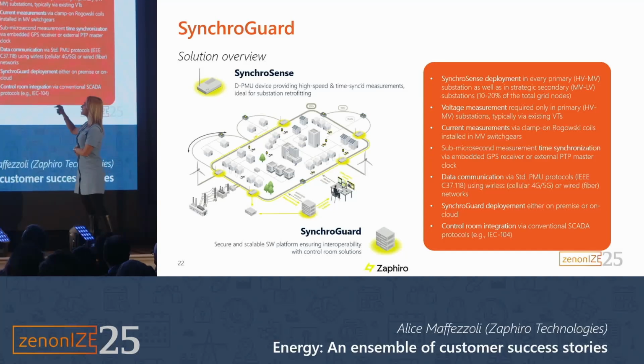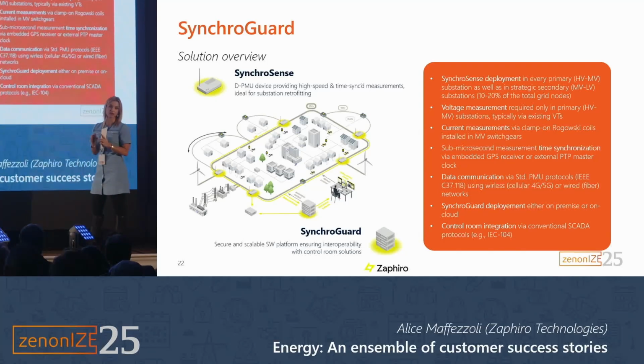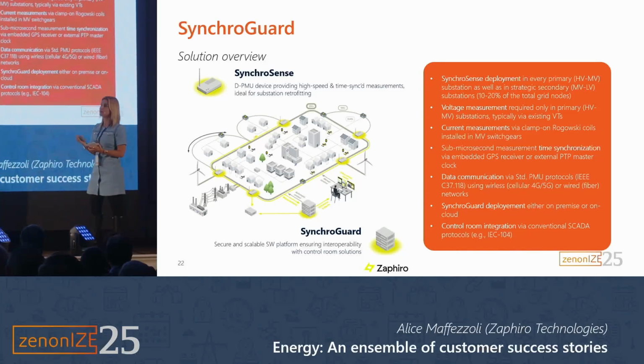So how does it work? Physically, we integrate one PMU in the primary substation, the high voltage to medium voltage substation, where we measure current and voltages. Voltages through conventional VTs that are available in the primary substation, and currents through Rogowski coils, so a non-invasive installation. Then, based on the single line diagram and the topology, we select some critical points in the medium voltage to low voltage substations, and we install PMUs only in these critical points. In general, with a coverage between 10 and 20%, we are able to get observability in all the grid, which means that we take measurements in 1 out of 5 to 10 substations. Thanks to the time synchronization, the precise measurements and our algorithm, we are able to estimate the transformer loading and line loading everywhere, in all the substations. So, as I said before, one PMU in the primary substation measuring current and voltage, and some PMUs installed in critical points only measuring currents.